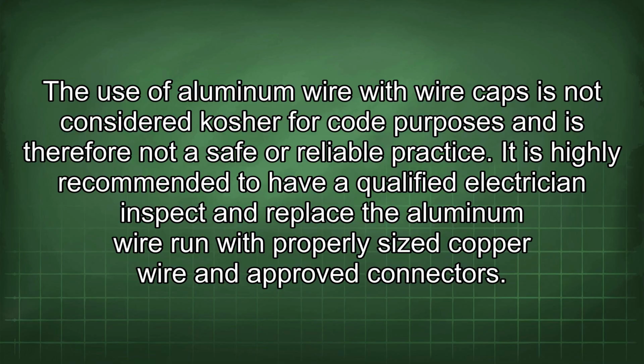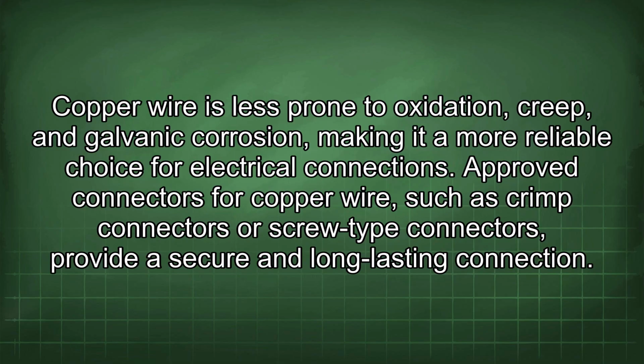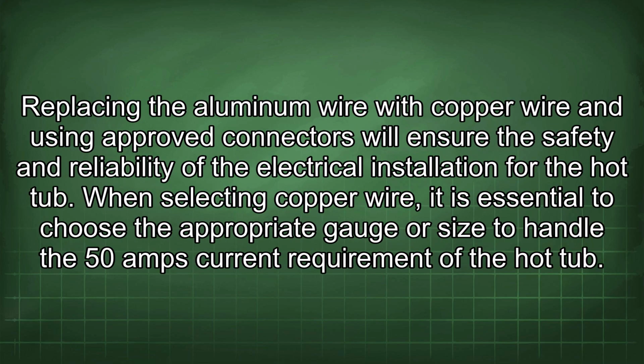It is highly recommended to have a qualified electrician inspect and replace the aluminum wire run with properly sized copper wire and approved connectors. Copper wire is less prone to oxidation, creep, and galvanic corrosion, making it a more reliable choice for electrical connections. Approved connectors for copper wire, such as crimp connectors or screw-type connectors, provide a secure and long-lasting connection. Replacing the aluminum wire with copper wire and using approved connectors will ensure the safety and reliability of the electrical installation for the hot tub.